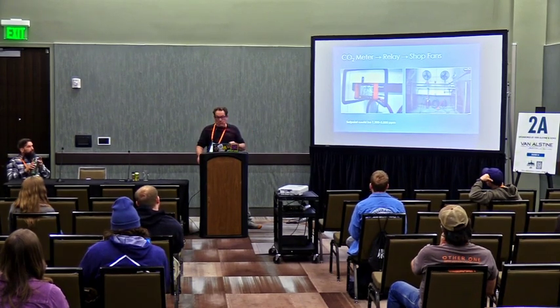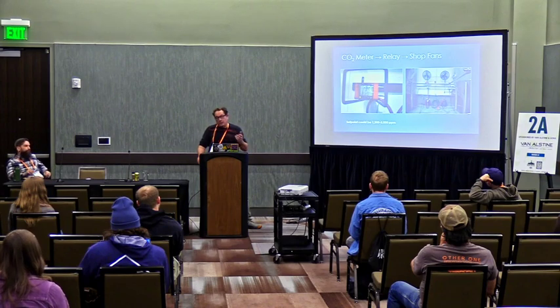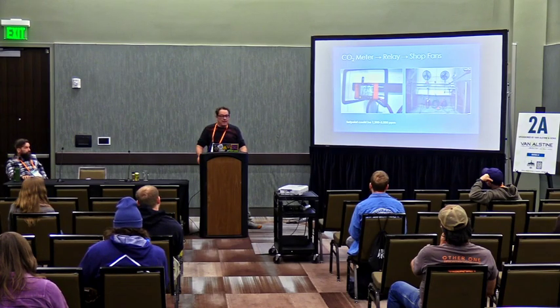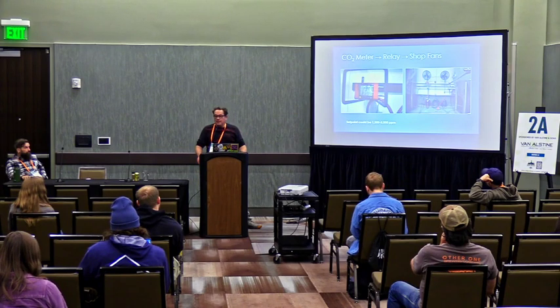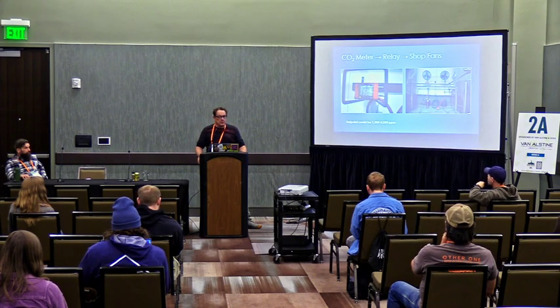This way, you can look at that number and go, well, at 2000 we turn on the fans. If you happen to look over at the monitor, which is all the way at the end of the cellar, and see it's at 2500, you know you need to turn on the fans—if you remember to, and if you know that standard operating procedure. In this way, we've automated it very simply, just using a relay from the output of the monitor.